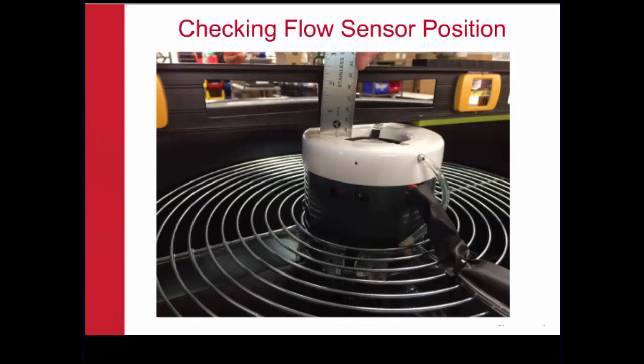So basically, taking a flat edge, and in this case we're just using a 24-inch level. The 24-inch level goes across the fan housing, and from the bottom of that level to the top of the flow sensor should be roughly 3/8 of an inch, plus or minus an eighth. That's your criteria. So you would measure that in 2 places or 3 places along the top of the flow sensor to make sure that it's in the right location.